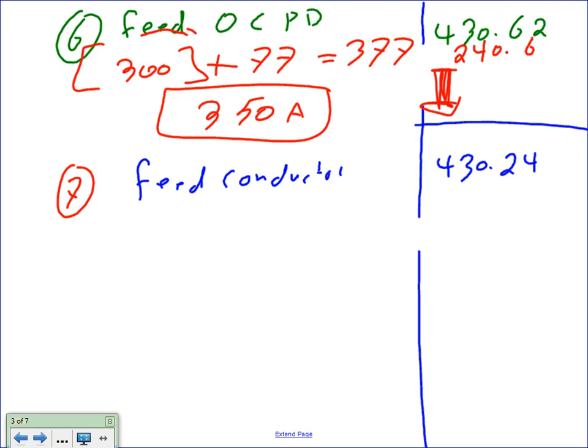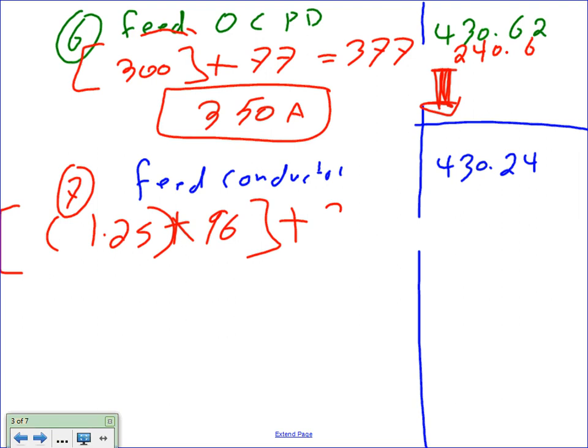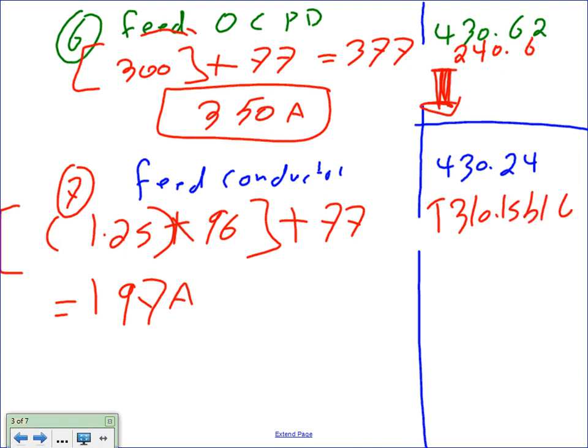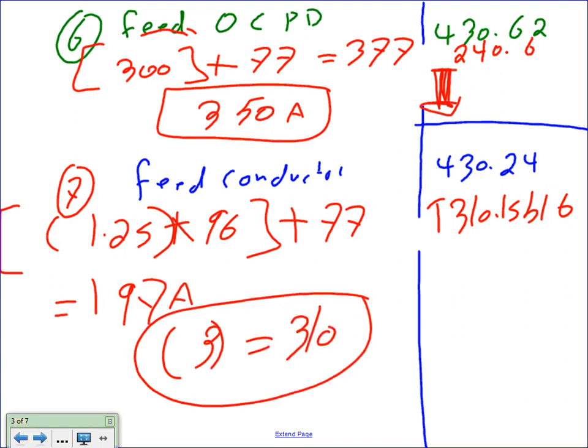You go down. The feeder, guys, the feeder conductor, you take 1.25, multiply this one by the largest, fattest motor, which is 96, plus, see where the multiplication goes, plus 77. If you do that, you're going to end up with 197 amps. And if you go to table 310.15(B)(16), right, under the 75-degree column, you're going to end up with 3 conductors. Each one of them is 3/0 as your calculation.